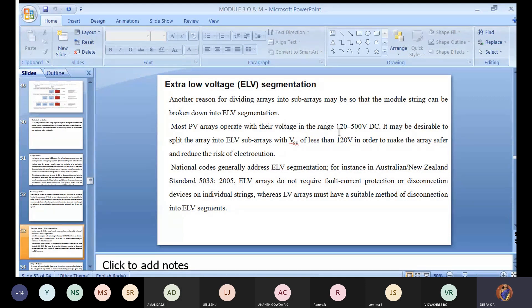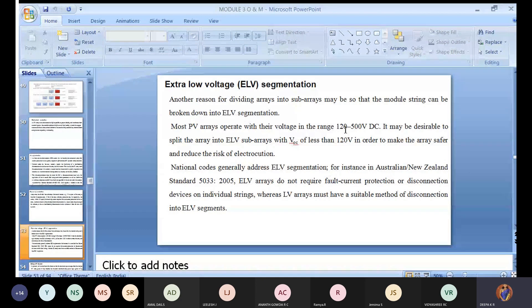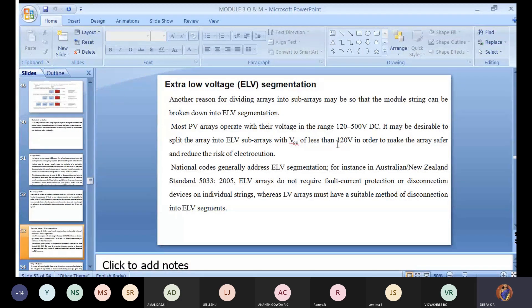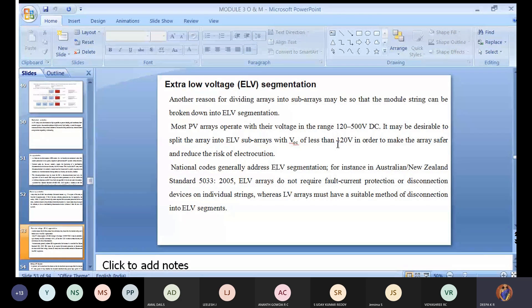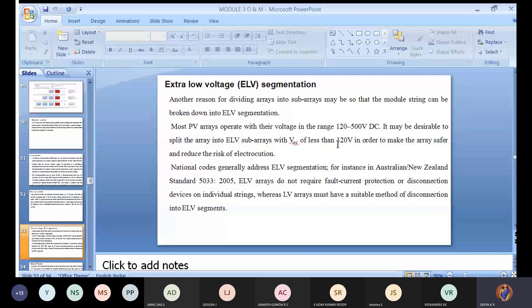Most PV arrays operate with voltage in the range of 120 to 500 volt DC. This is the range of the PV panels giving DC output, with 120 as the minimum and 500 as the maximum value. It may be desirable to split the array into extra low voltage subarrays with open circuit voltage of less than 120 volts.